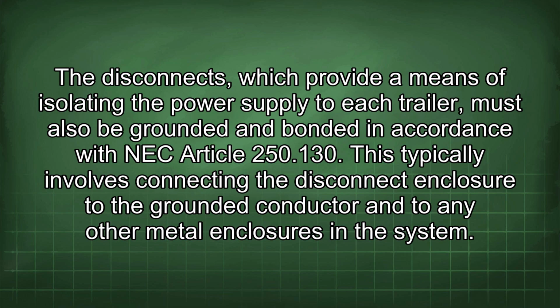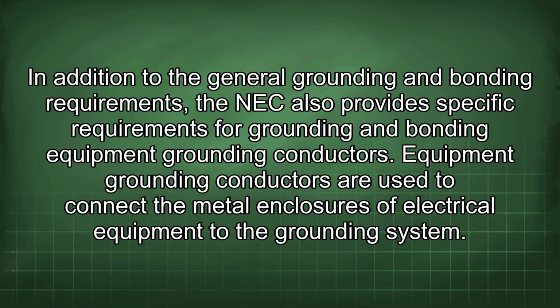The disconnects, which provide a means of isolating the power supply to each trailer, must also be grounded and bonded in accordance with NEC Article 250.130. This typically involves connecting the disconnect enclosure to the grounded conductor and to any other metal enclosures in the system.